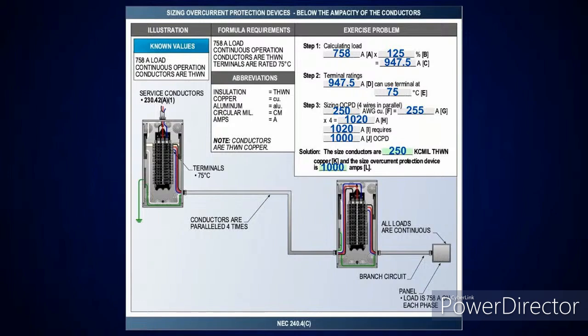Now, this is interesting because if you look at 240.4C, it says the conductors shall be equal to or exceed that calculated ampacity. So once you have your amperage value, which in this case is 1,020 amps, you can't exceed that. That means you're going to drop down to the next standard size, which in this case is a 1,000 amp overcurrent device. There are going to be some good rules of thumb when we get into sizing overcurrent protection devices in the next phase of this. But right now, we're taking Article 240 and explaining how you apply 240.4B and how you apply 240.4C.